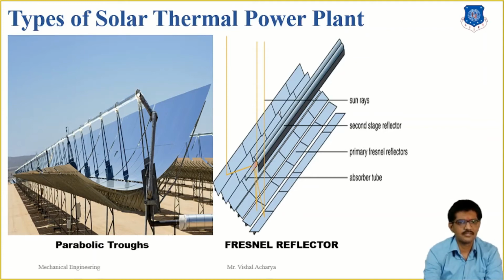In this, the United States uses a linear concentrator that uses the parabolic trough collector. In such a system, the receiver tube is positioned along the focal line of each parabola-shaped reflector. The tube is fixed to the mirror structure, and the heat transfer fluid flows through it out of the field of the solar mirror to where it is used to create steam, or in the case of the water steam receiver, it is sent directly to the turbine.